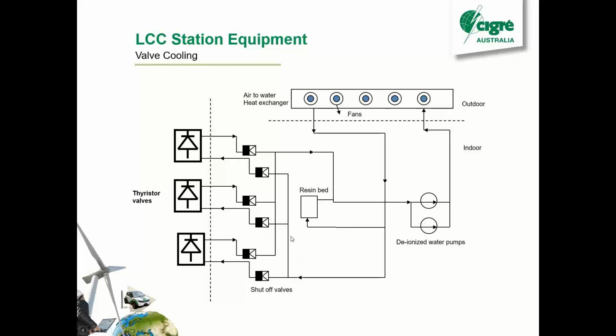So one of the main jobs of the valve cooling is to keep the conductivity really low. We do that with this resin. There's a tap off that's cleaning the water all the time. And you monitor the conductivity in real time, and if it gets too high, you have to trip.